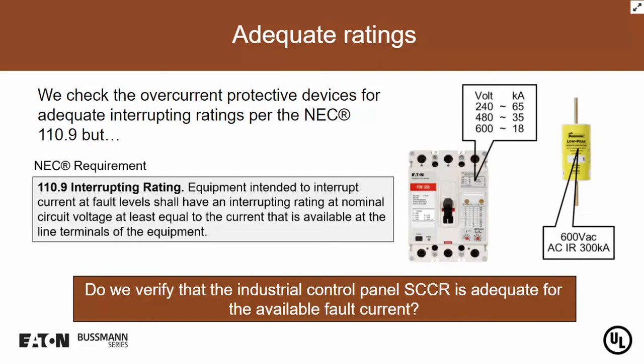So basically, like John said, if we had 50,000 amps available, our fuse is rated for 300,000 amps, we're good to go. And if we're in the breaker, if we're on a 240 volt system, the 50,000 amps is adequate as well, because in this case, the breaker is rated for 65,000 amps at 240 volts. If we're at 480 volts, then we're at 35,000 amps, and for a 50,000 amp fault, the breaker is not adequate, and we would have to change out the breaker and put in a higher rated breaker at the 480 volt level itself, right?